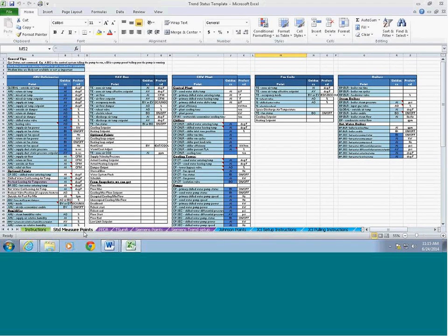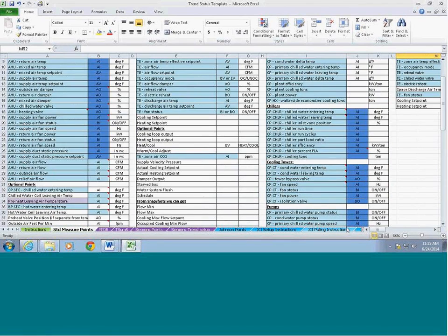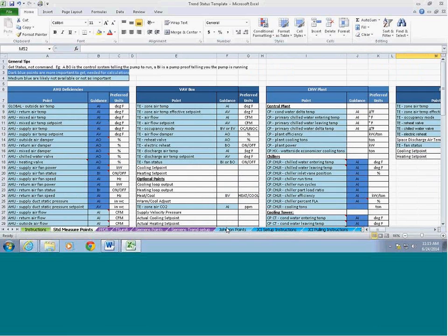Just as we're looking at this list, if you're selecting trends, inputs, analog inputs, binary inputs, multi-state inputs, those are generally best for identifying actual operation for sensed values. For instance, if you want to know what the speed of a VFD is, an input is a way to know you're getting feedback from the drive, what it's running at, not just what the control system is telling it to do. There's always an opportunity for something to be manually overridden or bypassed.